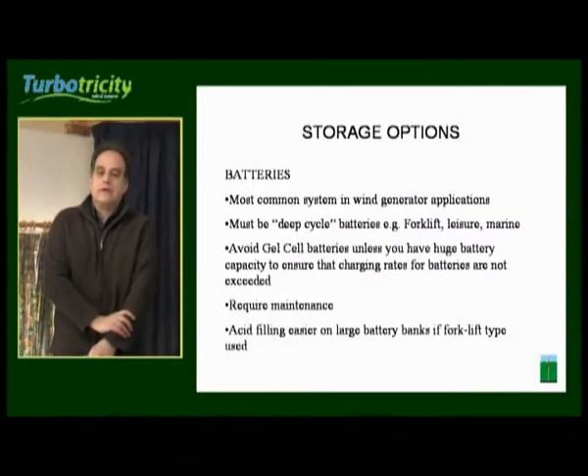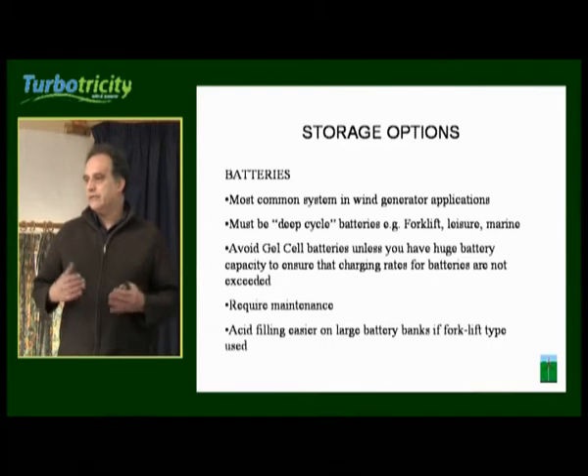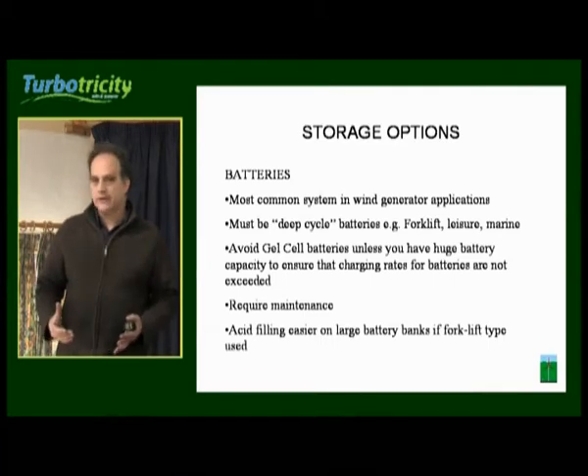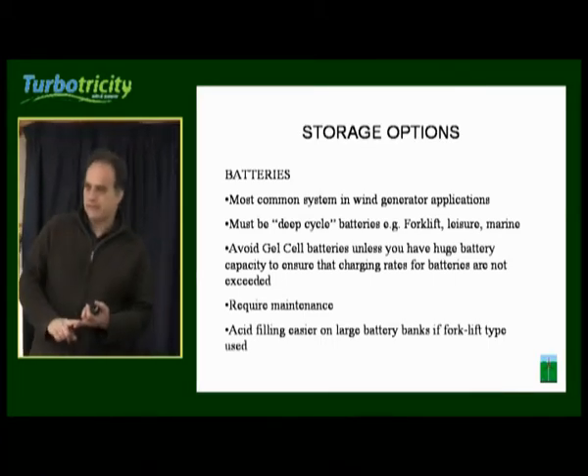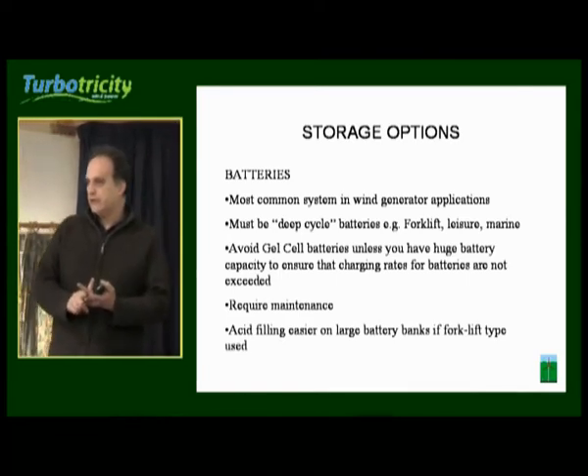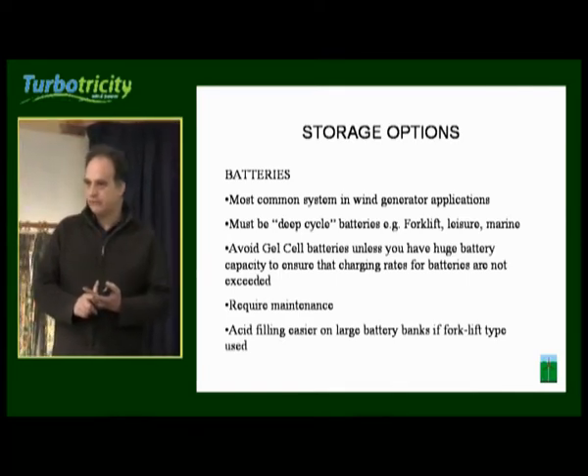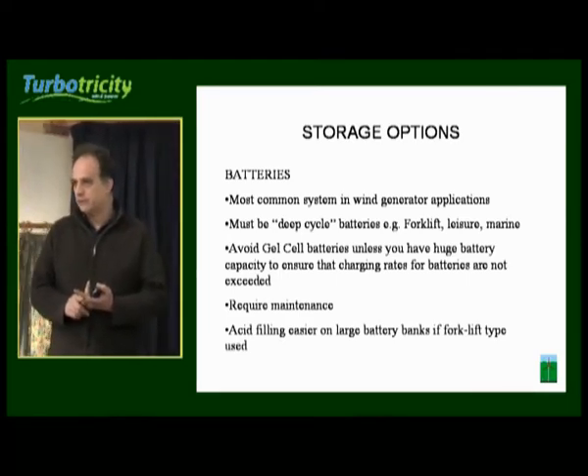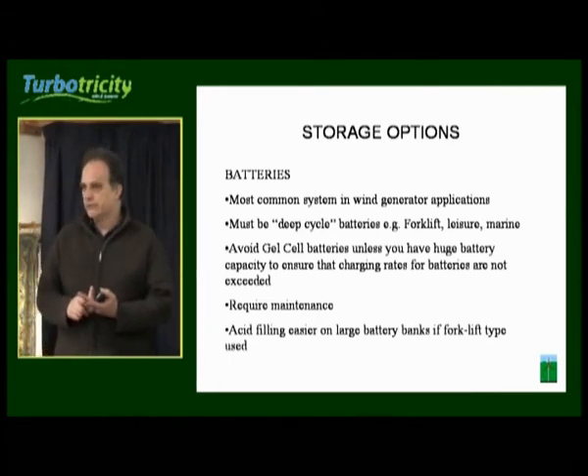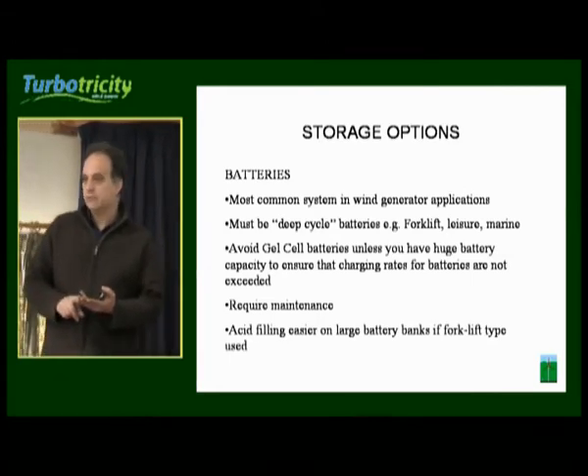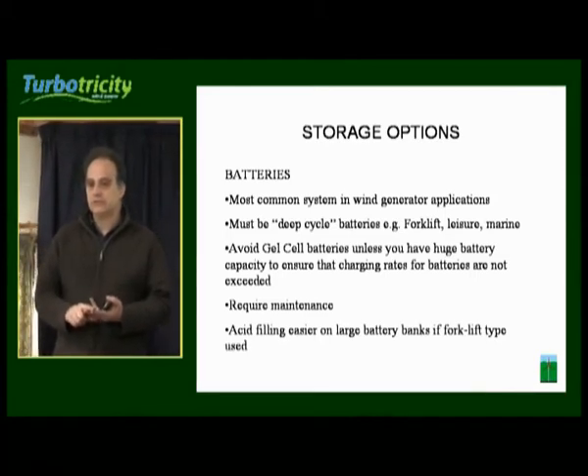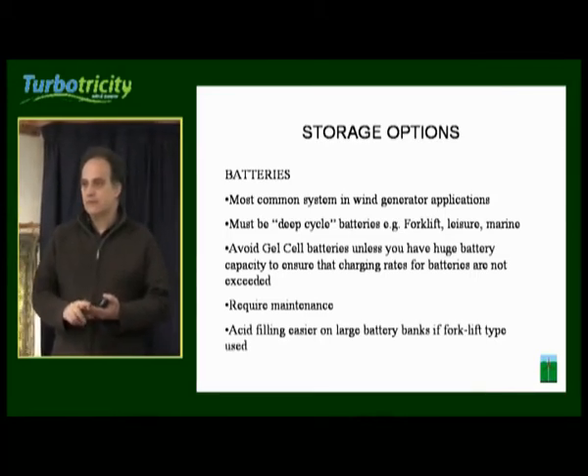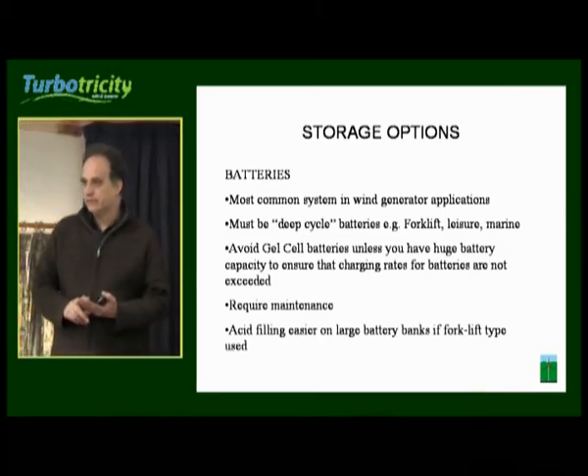The batteries used have to be capable of withstanding deep cycles. The kinds of batteries designed for deep cycling are forklift batteries, leisure batteries used for boats for lighting when in harbour, or golf buggy batteries. Various batteries designed for deep cycle are what you must use for a battery-based system.